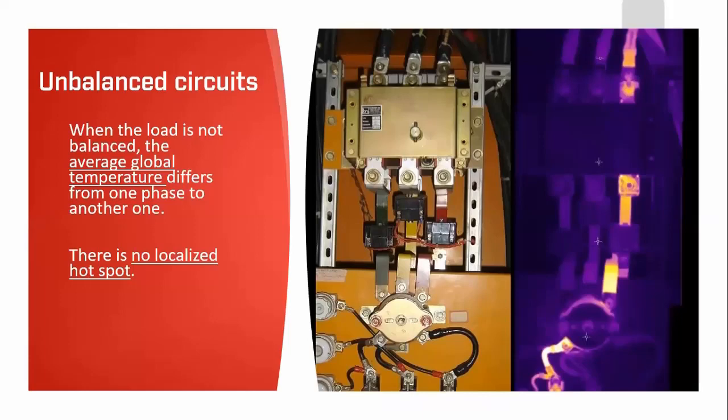When the load is not balanced, the average global temperature differs from one phase to the other. Looking at this thermal picture, we can clearly see that the right-hand phase is warmer compared to the others, and there's no real localized hot spot — it's a general phase temperature difference.